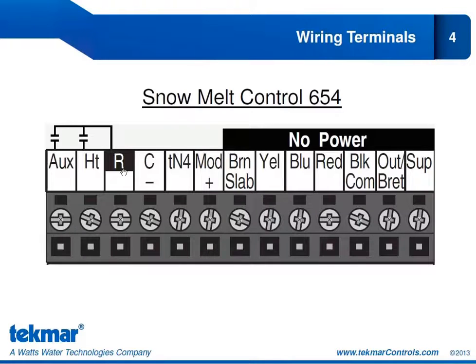Now, because we are tied to an R, if we're using the heat relay to provide an enable signal to a boiler, we don't want that to be a wet contact. We want a dry contact, so that would require an isolation relay. And if we are using the auxiliary relay to go to a pump, then our 24 volt is obviously insufficient and we would need another isolation relay for that. And we'll take a closer look at that coming up here.